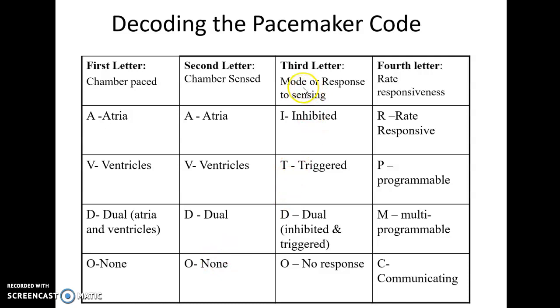The third letter is going to be the mode or response to sensing. So what that means is if you have an I there, it means it's going to inhibit itself. So let's say I have an atrial pacemaker and it senses the person's own atria, it will inhibit itself from firing.